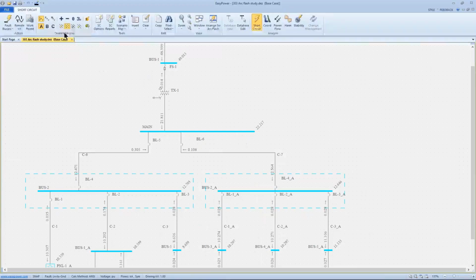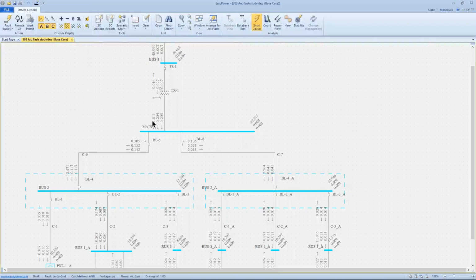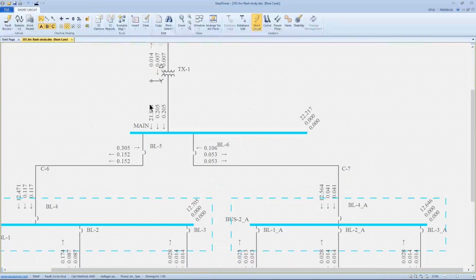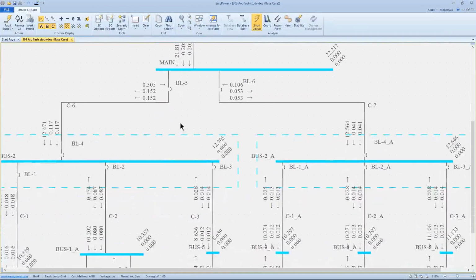Line to ground fault, on the other hand, will show in the three phases different fault currents. In this case, the high current phase will be that which is grounded, and the other two will show relatively low current because of the zero voltage on the bus.